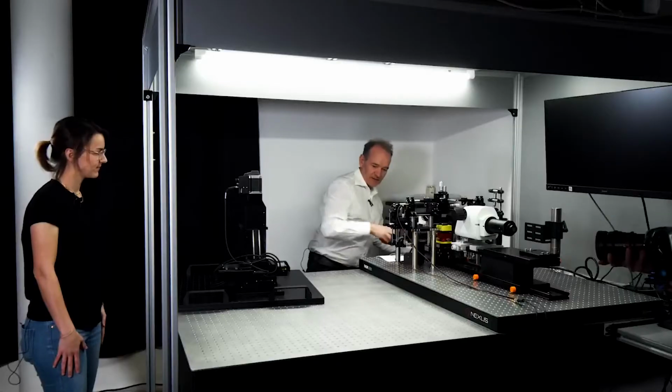But actually, because the laser and everything is all put together in a single frame, the microscope is inherently very stable. So actually, you don't really need a vibration-isolated optical table. It's fair enough when you just have a relatively quiet environment, and you should get decent images with it.